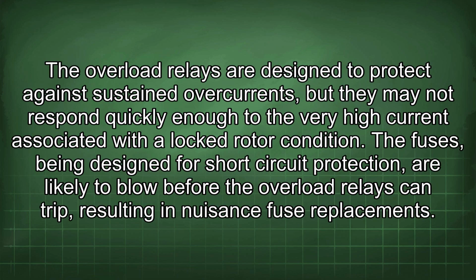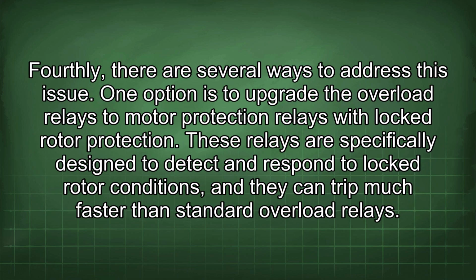The overload relays are designed to protect against sustained overcurrents, but they may not respond quickly enough to the very high current associated with a locked rotor condition. The fuses, being designed for short-circuit protection, are likely to blow before the overload relays can trip, resulting in nuisance fuse replacements. Fourthly, there are several ways to address this issue.